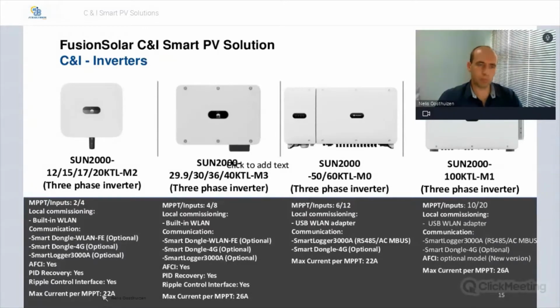The latest PV modules, which is about 600 watt, they've got a higher short circuit current of about 13 amp. So you will still be able to use them, but then you might only have 1 string connected on the MPPT, because as soon as you connect the 2 strings, the current will add up and you'll have 26 amps. So please note that on the smaller size inverter. So going over to the next range in the C&I, which is more intermediate range, it's ranging from 29.9 or 30 all the way to 40.